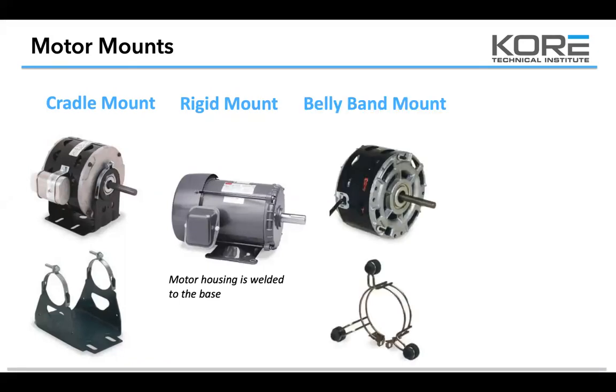And the belly band mount, which we've seen a lot of, like condenser fan motors and stuff. The one thing I will tell you guys is, understand if you're dealing with a fully enclosed motor or an open motor. Understand some of those motors are directional depending on how they oil the bearings. So if you tip them upside down or sideways, you need to understand what direction they need to be sitting, because if you do the wrong thing, the oil will not be up against the bearings. It'll run dry. It'll wipe out the bearings. You'll be back there in a couple of days.